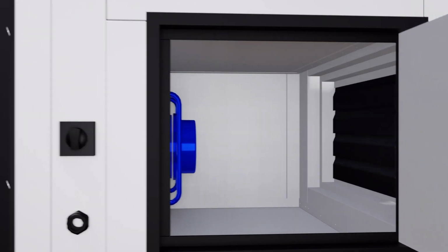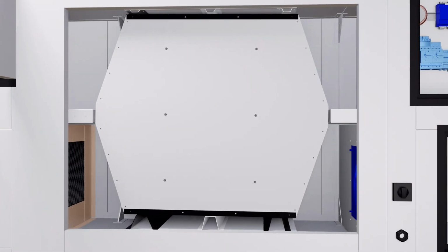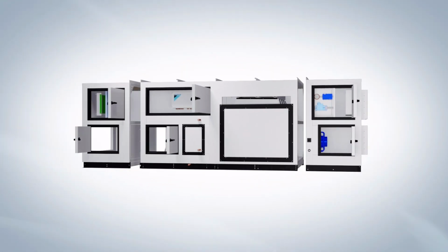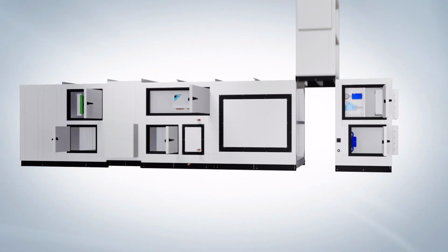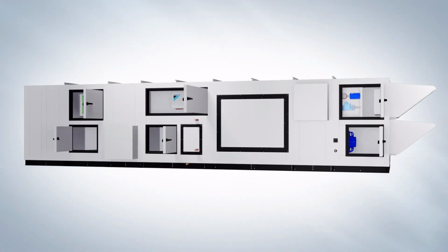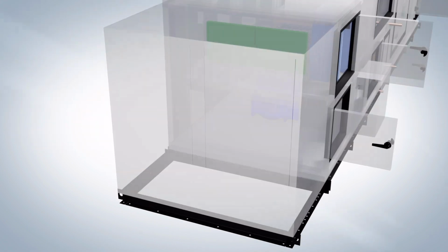The modular design of Ventum Plus allows for easy integration of heating and cooling solutions by simply adding modules to the base unit design. Select from electric or hydronic pre- and post-heat, in addition to Daikin's VRV with DX and optional hot gas reheat, using factory-integrated electronic expansion valves and controllers to achieve accurate temperature and humidity control. For outdoor applications, downshot modules can be selected as standard.